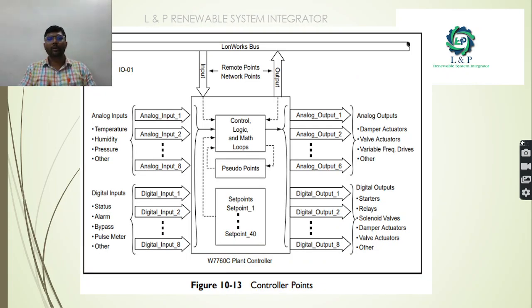Next, if you are going for controller points, okay, as we told earlier, normally it is either a BMS controller or a DDC controller or, most importantly, a PLC controller, okay. It has a CPU, it has a memory, it needs a power supply to run, and it can be random access memory or read-only memory as well, okay. And most importantly, with the LAN network we are establishing input and output connections with the controllers. So the controller has the capability to do so many mathematical operations: addition, subtraction, multiplication, division, logical operations, pseudo points, set points, like that. So many operations a controller can make, okay.